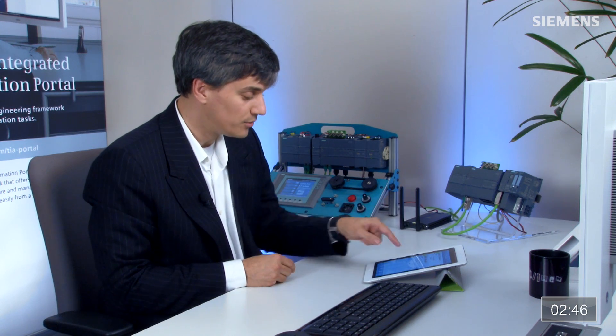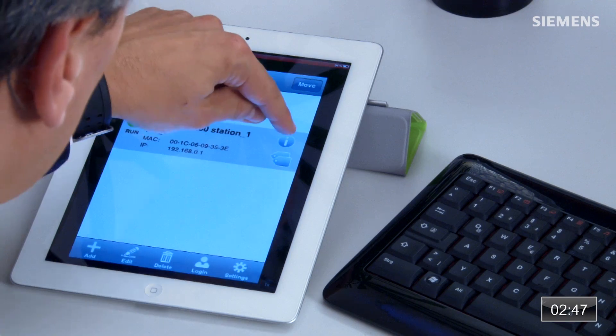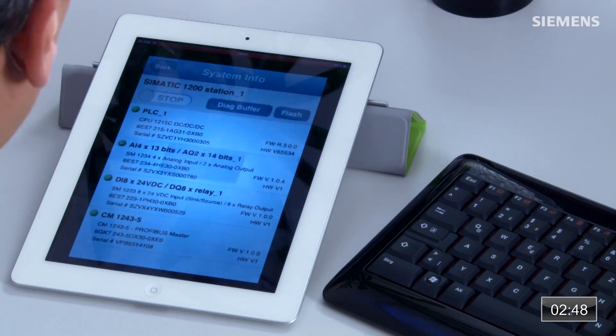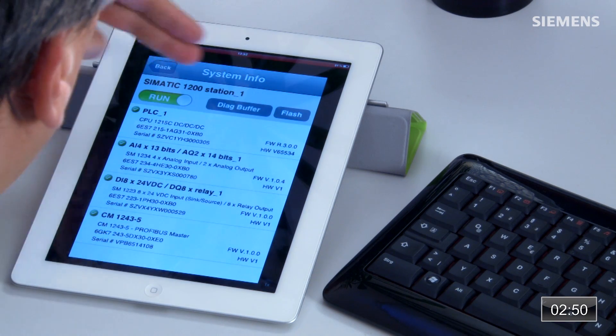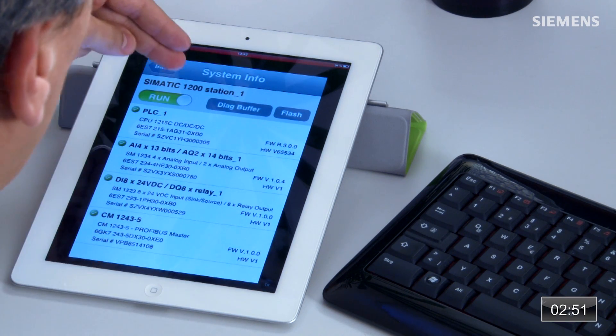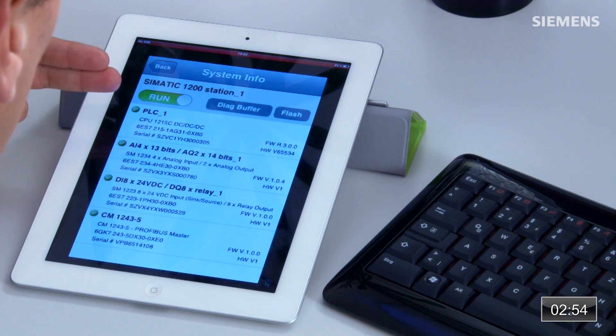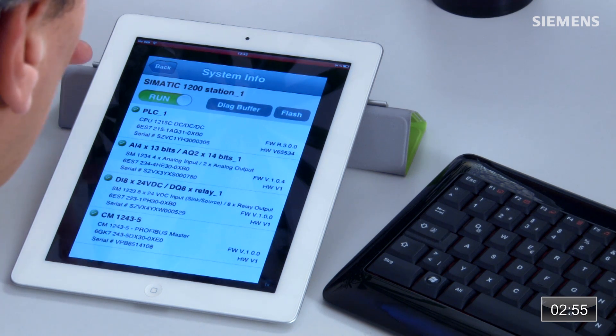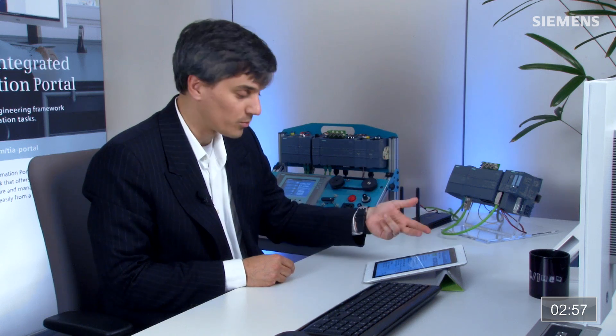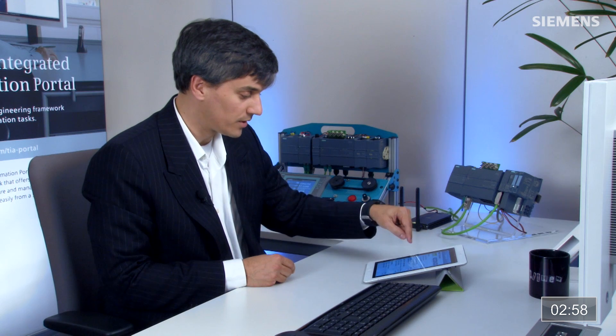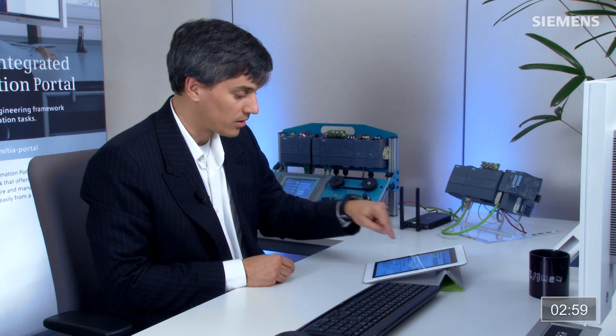If I want to interrogate the new controller, just click on this icon. You can see across the top we have the run/stop state and a diagnostic buffer. We also have the controller with all the part numbers, serial numbers, hardware and firmware versions, including the analog card, digital card, and a Profibus Master card. Everything is correct and good to go.